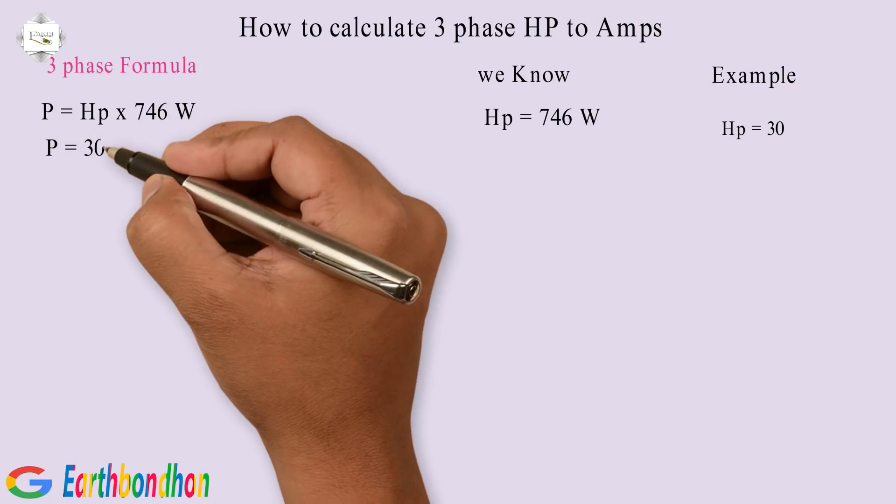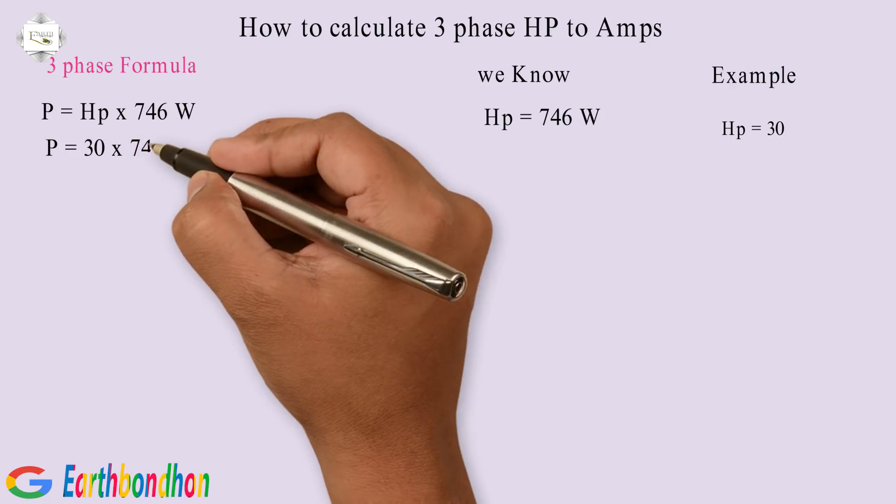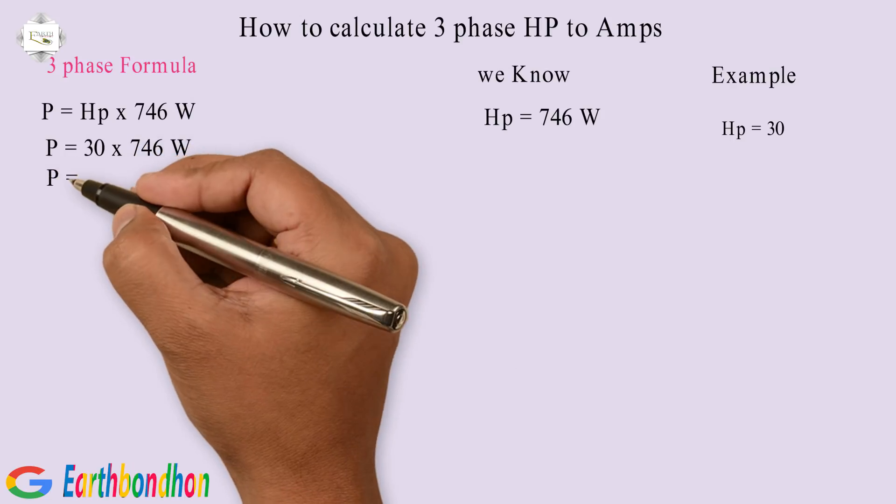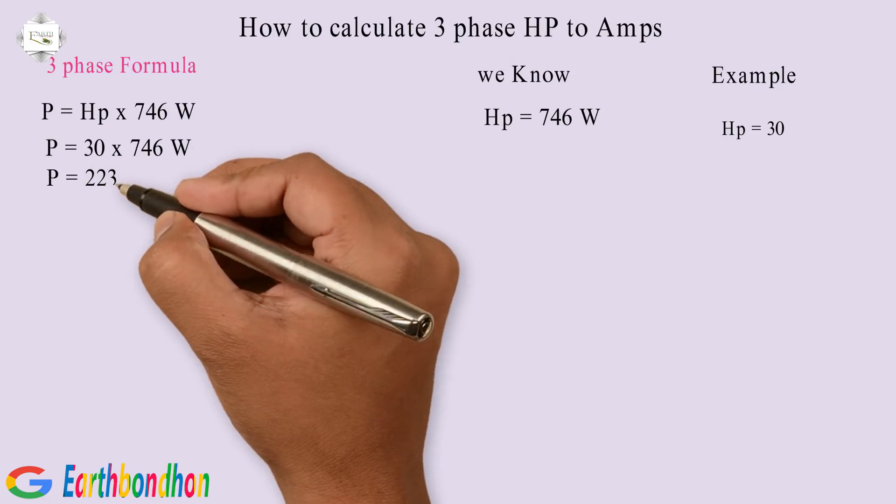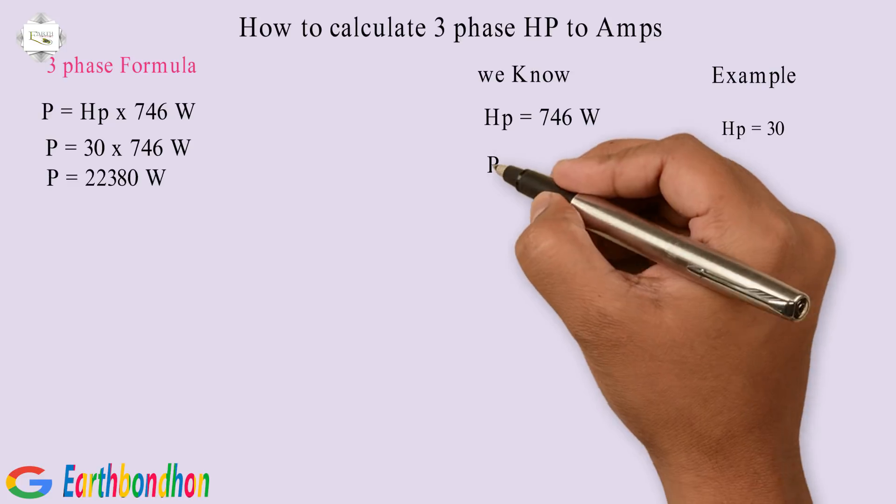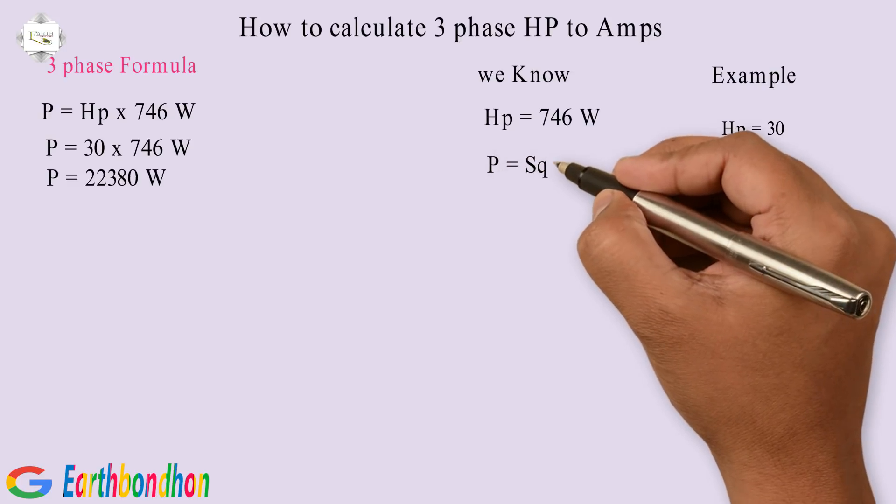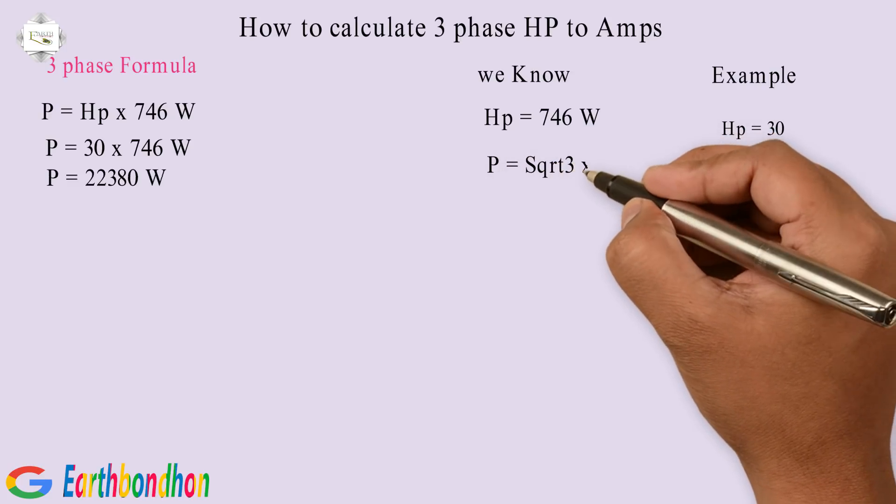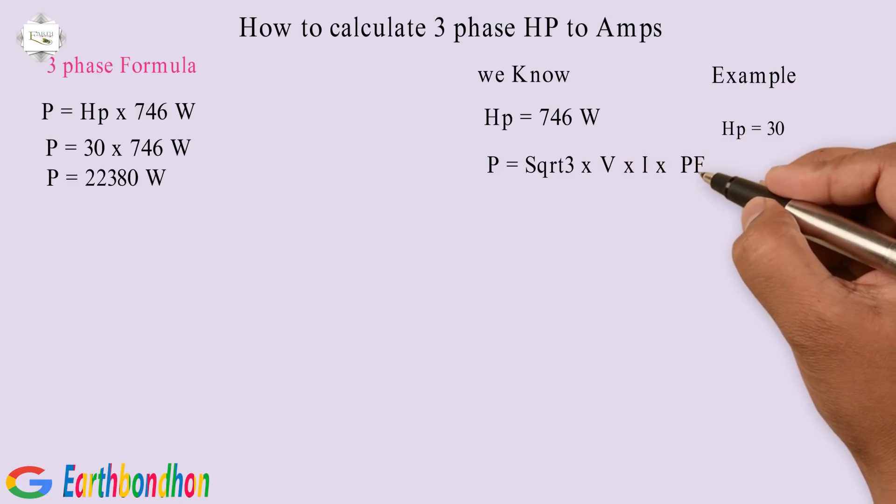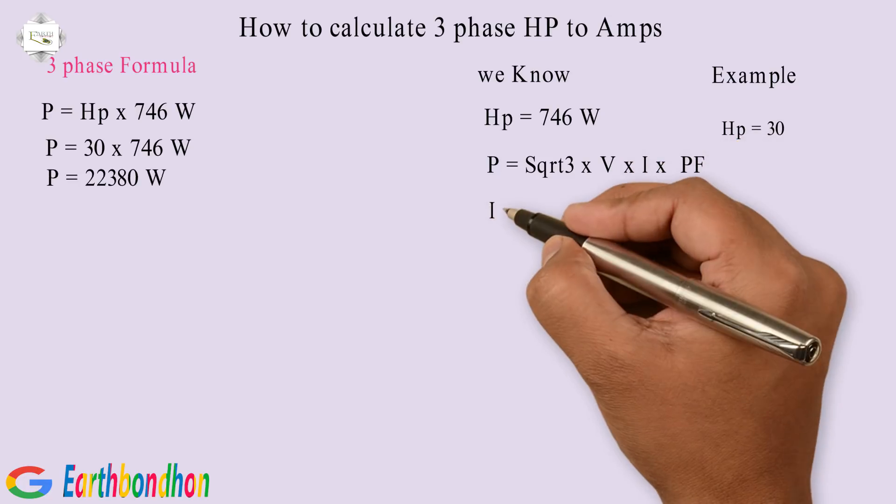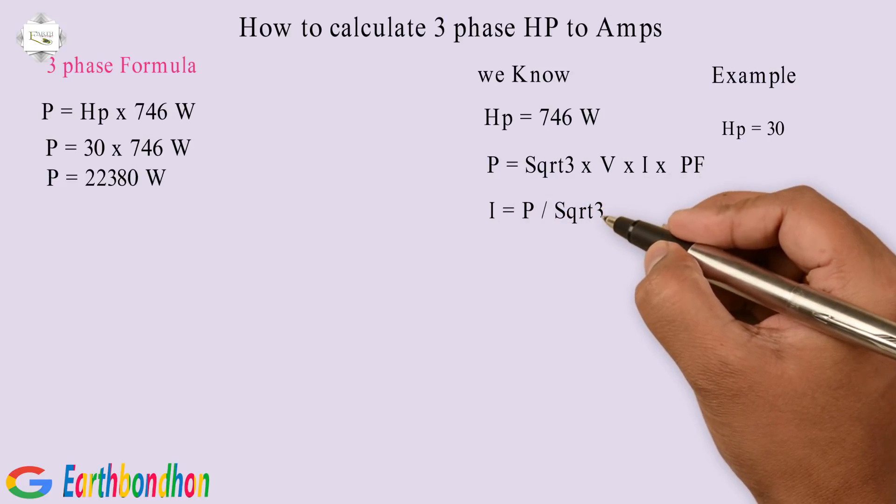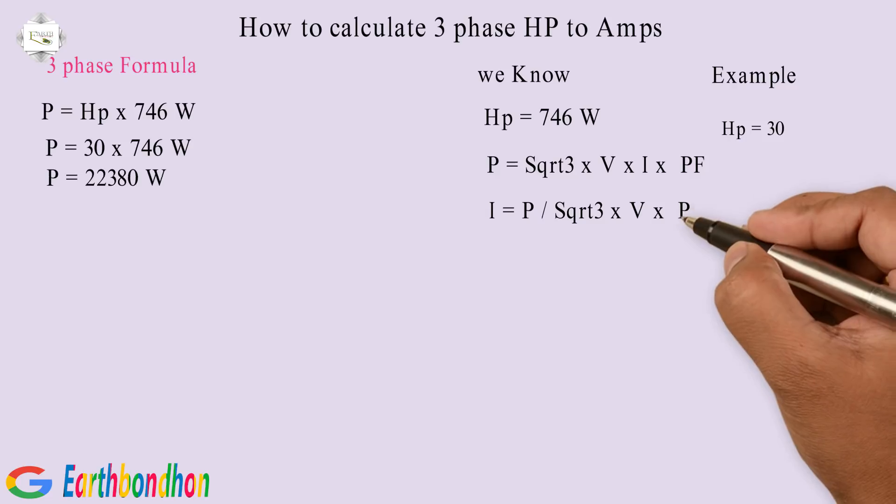Power equals 30 multiplication 746 watts. Power equals 22,380 watts. P equals SQRT3 multiplication volts multiplication amps multiplication PF. I equals P division SQRT3 multiplication V multiplication PF.